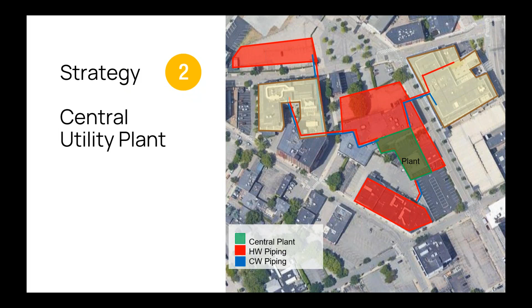In every building, of course, you can't do much with the ambient water temperature directly. You can't heat or cool with it. However, you can exchange heat. In an example like the jewelry district, where there's a wide variety of different building usage, a mixed-use portfolio of buildings, that loop allows you to transfer energy between buildings—unused or excess heat that one building may have can be transferred to another building that may be in heat demand at some point.